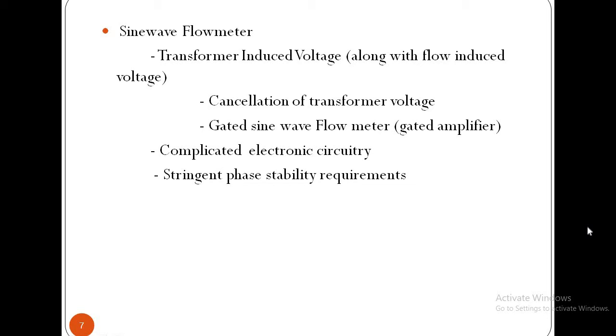The sine wave flow meters require complicated electronic circuitry for the removal of transformer induced voltage from the flow induced voltage. As both the waveforms are of the same type, complete elimination of the artifact voltage becomes extremely difficult. The sine wave system no doubt yields good signal to noise ratio but imposes stringent phase stability requirements with increasing frequency.